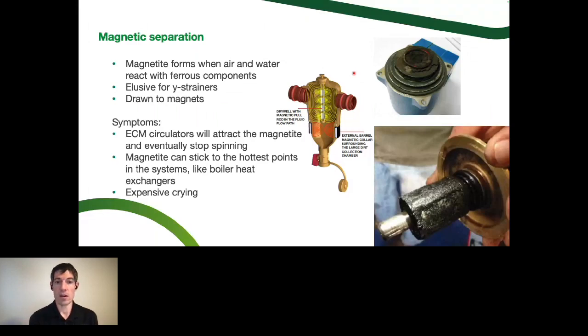Now we've got this great new technology with modulating condensing boilers and ECM circulators. The problem is we have a lot less margin for error there. We've got smaller passages through a heat pump or a modulating condensing boiler. This magnetite can cook to the inside of the heat exchanger, or it can get stuck on another magnet. So ECM pumps have a big magnetic component that is going to attract this magnetite, and it's going to get stuck to the rotor. This is actually from our building in Caleffi in Milwaukee, an ECM circulator that failed on us, and we were wondering what happened. We opened it up. This was at the time a 5-year-old building, but there was some steel piping and there was an air issue because we had a leak that we took some time to track down, even in our own building.